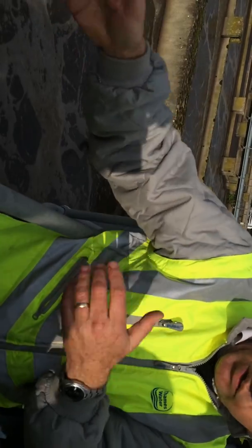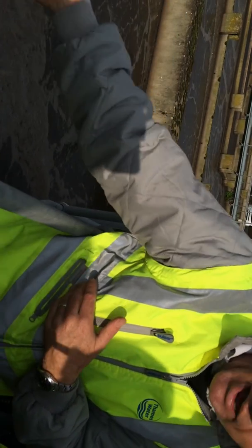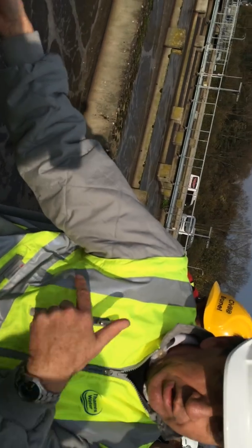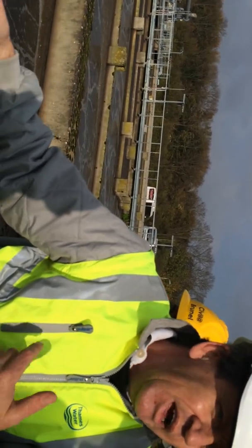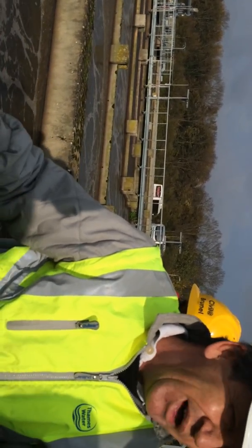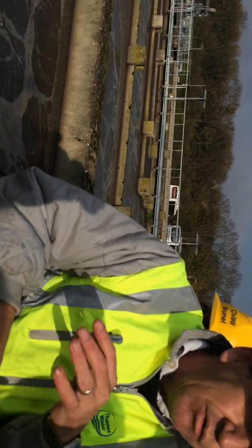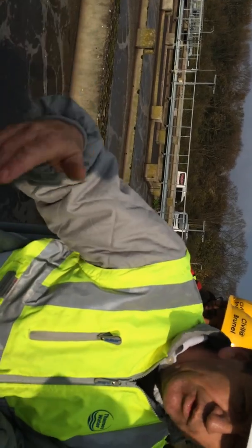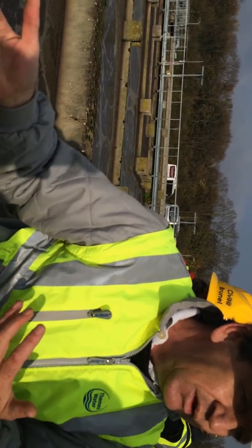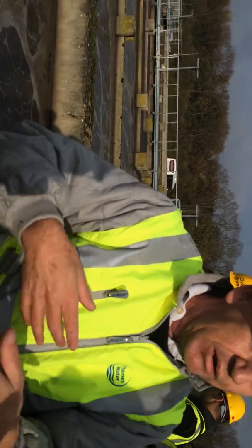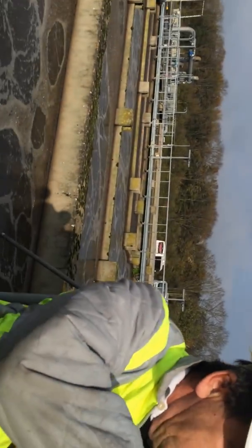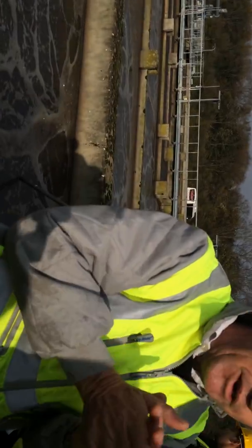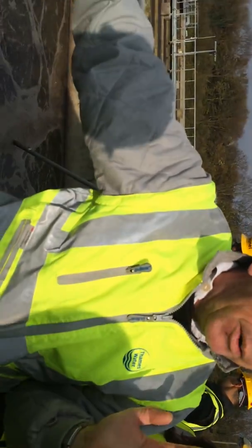And then these sort of wastewater temperatures, at the moment the wastewater temperature today is probably about 14 degrees. But on a big site like this, it will get down to 11 or 12 degrees, not much lower than that even in January. But at that temperature, their growth rate is slower. We would need to maintain the sludge age at about 10 or 12 days to keep the nitrifying bacteria in the system. So the final clarifiers behind us are absolutely essential for separating the biomass out so we can return it back to the process.